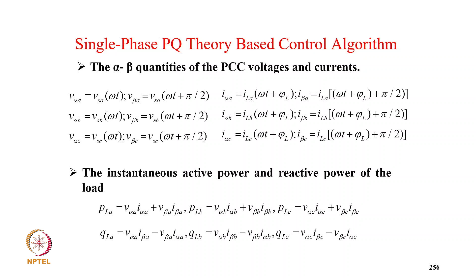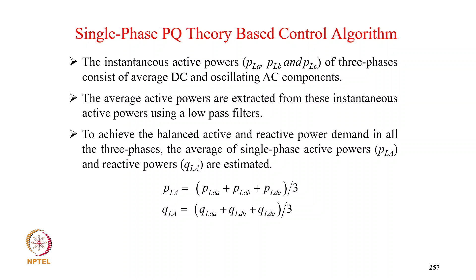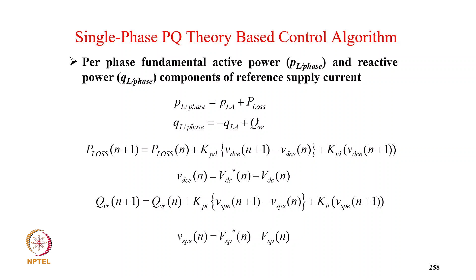From the voltage we get V alpha and V beta. Similarly for the current we get alpha and beta, from which we get the active power of the load for the three phases. Then the reactive power, also for the three phases, and then we sum all three to get the total active power. From the low pass filter we separate the fundamental. Similarly for reactive power, and then we have the total power as loss plus load active power. Similarly for voltage regulation, the reactive power for voltage regulation minus the load gives the net reactive power on the supply. So these are the two PI control equations to get the loss component and the reactive power component. Then from this we get the three-phase reference supply current, and with the feedback current we have the current control.